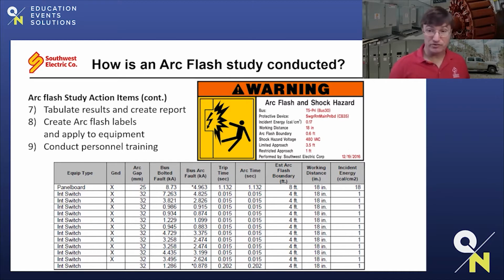In addition, based on these results, an arc flash label is generated. That was one of the six steps of compliance from the NFPA 70E standards. On this label, and you see an example of it on your screen, that's going to let you know what specific bus it applies to, the amount of voltage that that bus operates at, and then all the characteristics. What was the incident energy level? What is the limited approach, the restricted approach, and arc flash boundaries? And what was the date that this arc flash assessment occurred? So you know how old or how relevant that study is. Once these labels are affixed to all the appropriate equipment throughout your facility, training should also be followed up so that everyone in the facility knows what these labels mean, know what their values mean, so that everyone can stay safe around this equipment.